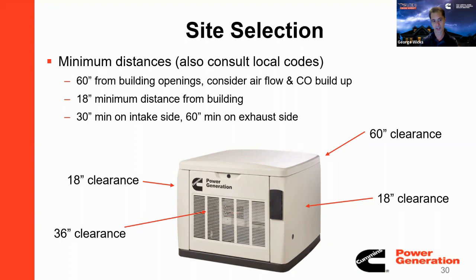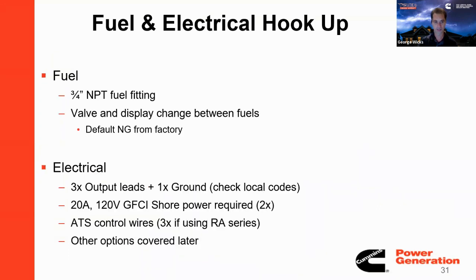On the sealed sides there, you can see we have an 18-inch clearance, and that was the parallel airflow I was talking about. We don't want to rotate the unit to where it's either breathing air in directly from the house side or discharging the hot air towards the house, because you're going to get into carbon monoxide buildup. These houses are pressurized so tightly that when their systems run, they seem to suck air in anywhere they can, and our CO coming off our units can trickle in through some of those air gaps.